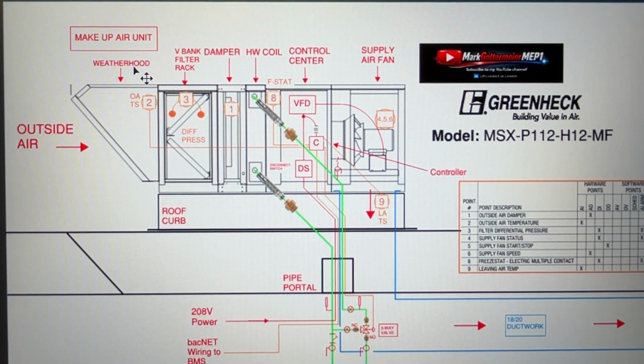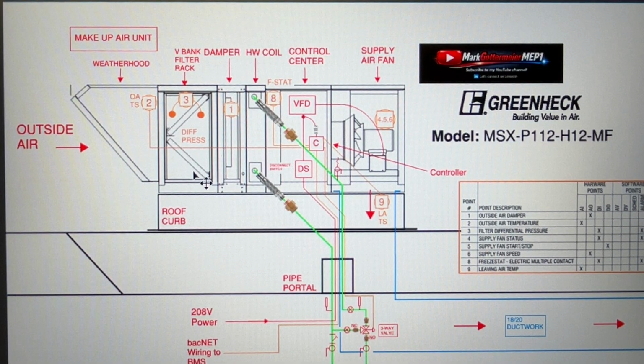So if you look up here at the top, I have defined all the chambers of the makeup air unit and what they do. So our outside air coming in, there is a weather hood here. Then we have our V-bank filter rack, which has those filters in the V shape versus your standard flat, which is pretty common. Then you have your damper. This will be a louver that opens and closes the fins of it to allow air to pass through. When the system's off, that damper will close.